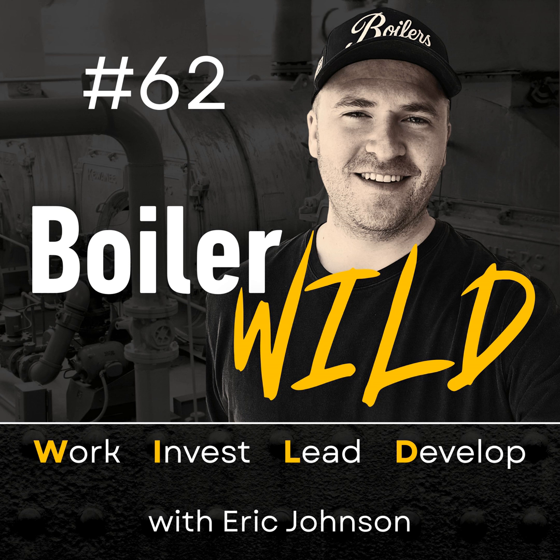And this list that I made is for a typical power burner boiler. Very, very popular, a package burner, package boiler. If you have a high efficiency condensing boiler with a special system and special setup and everything, it's going to change a little bit. If you have an atmospheric boiler, it's going to change a little bit, but the basics stay the same, and you just need to understand the core fundamentals. I always talk about understanding the basics. What needs to happen all at the same time in order to reliably light pilot and then transfer over to main. So let's go through the list.